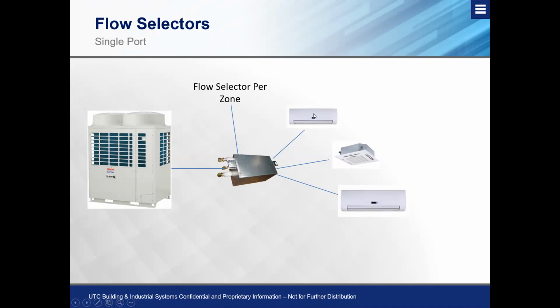These all have to be in cool or all have to be in heat. So it's important to know that these units, while they can have 3 on one single port flow selector, need to experience the same thermal demand. Essentially what that means is either all in heat at the same time or all in cooling at the same time. If you have a situation where this one needs cooling and these 2 need heat, or vice versa, these need to be on their own individual ports, either through individual selector boxes or we select a multi-port flow selector box, which allows each indoor unit its own individual port or selector. So we talk about the flow selector per zone. These are all experiencing the same temperature, which may be a problem. But if you have those diverse thermal loads, that's when you can start running the issue with expectations versus what the actual equipment can do when we're looking at a single port box.